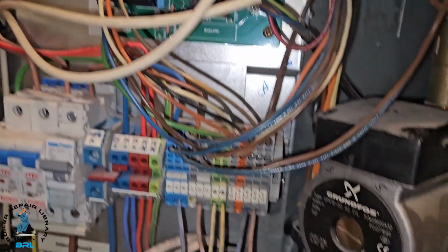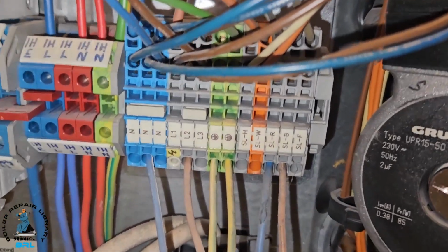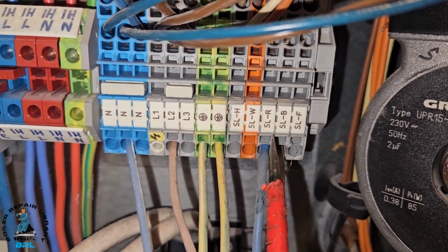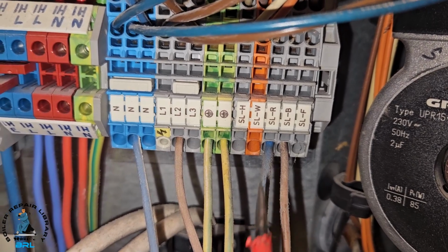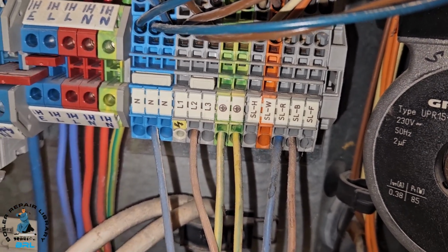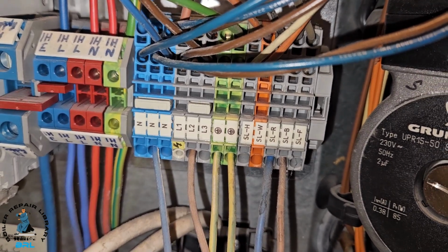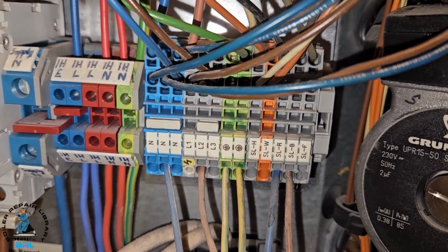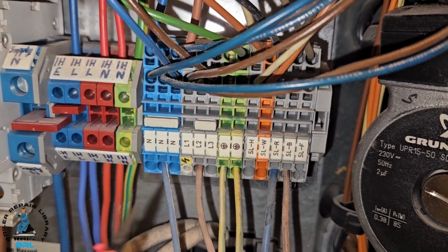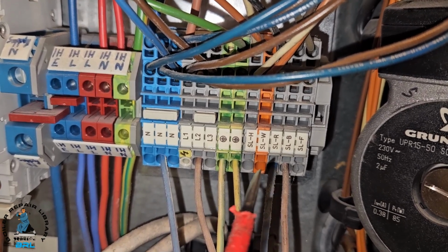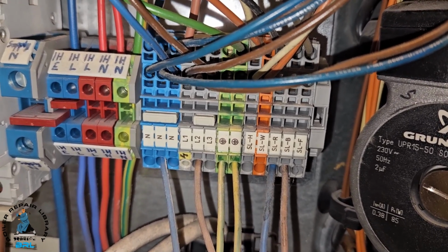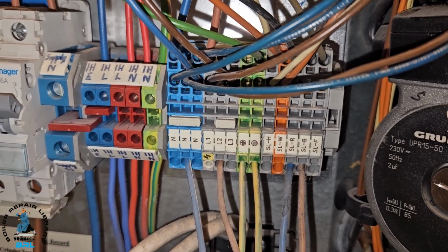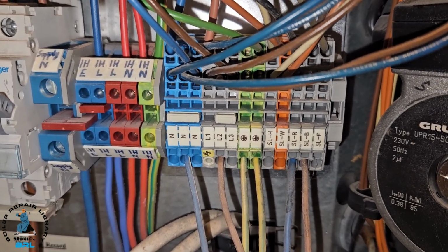If we go down, this is the DIN rail, and if you look at this one here, SLR, that switch live return is basically the wire coming back from the room thermostat saying that the thermostat's working. So we're going to go across to neutral on this side and put my multimeter on this SLR to see if we're getting power coming in from the room stat, which we should be because we linked out the room stat, but we'll just confirm.